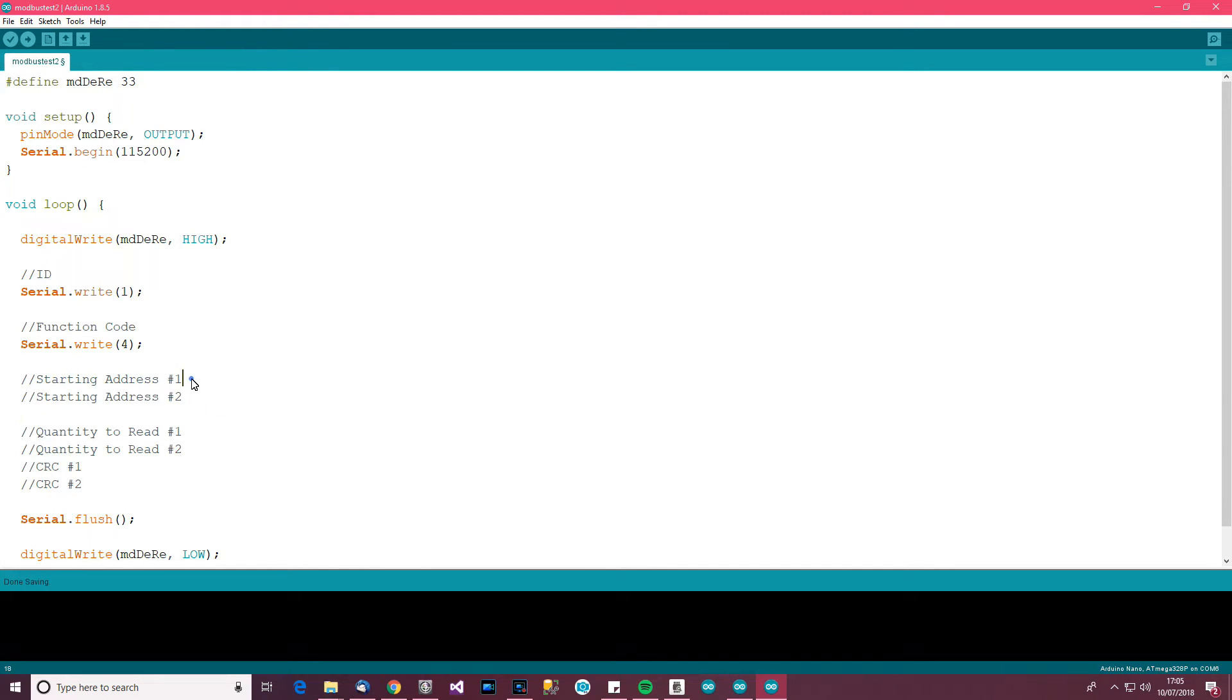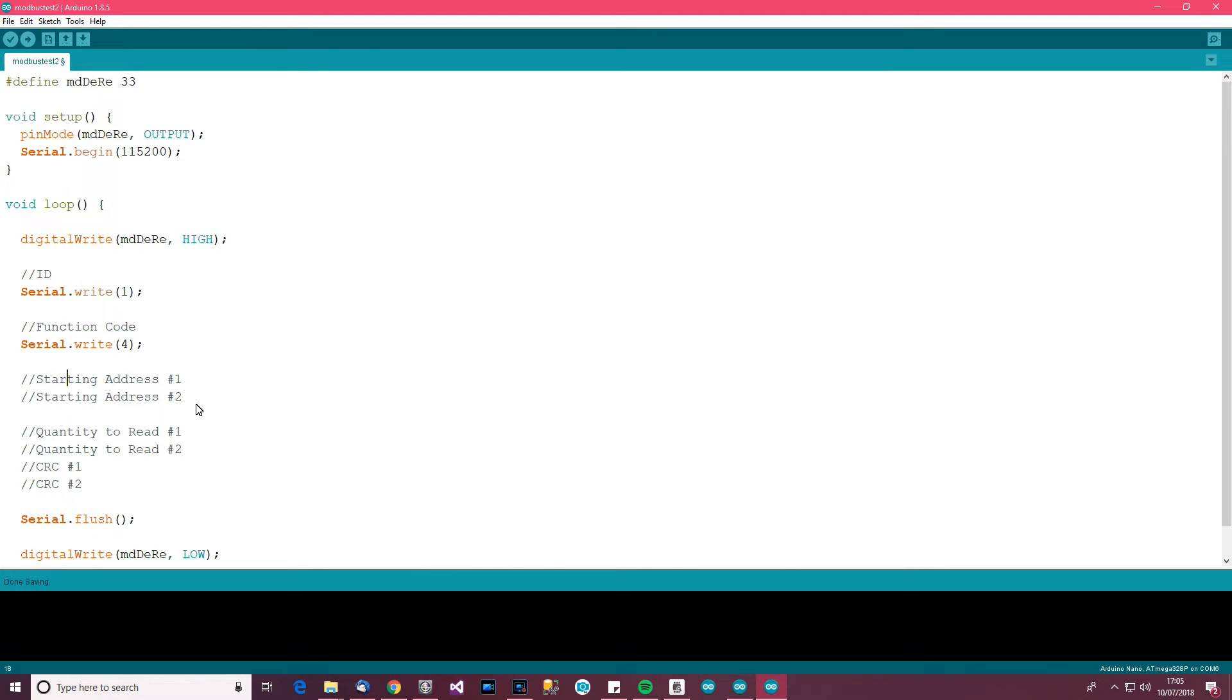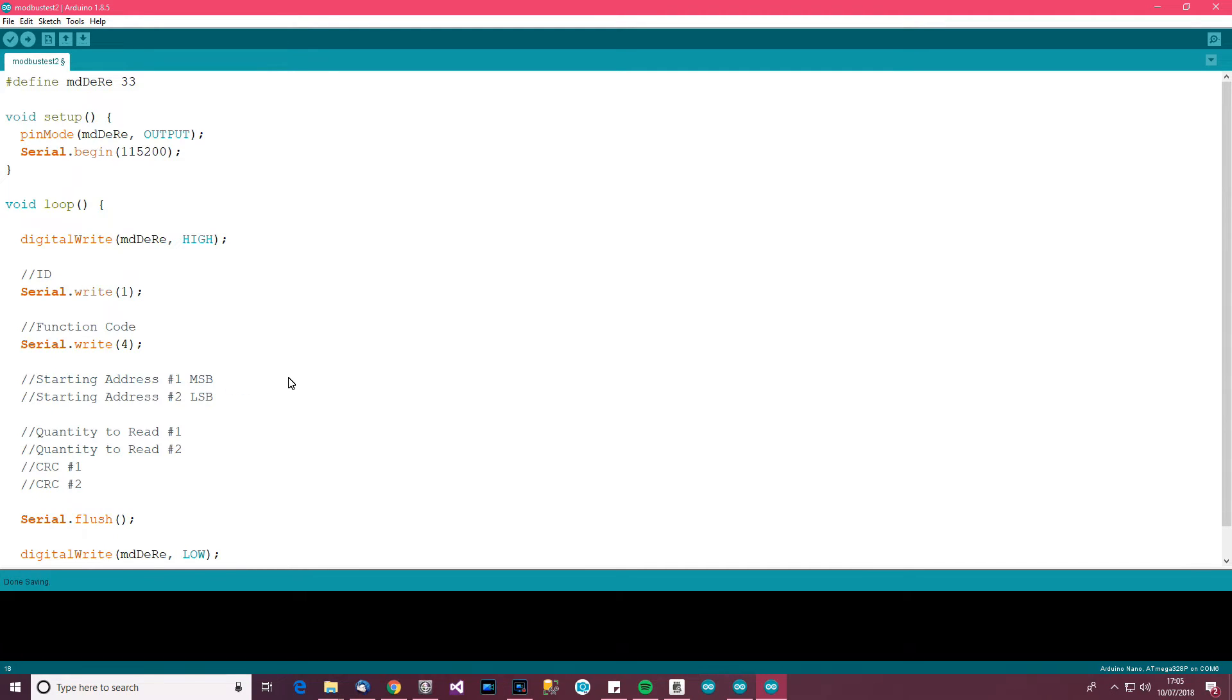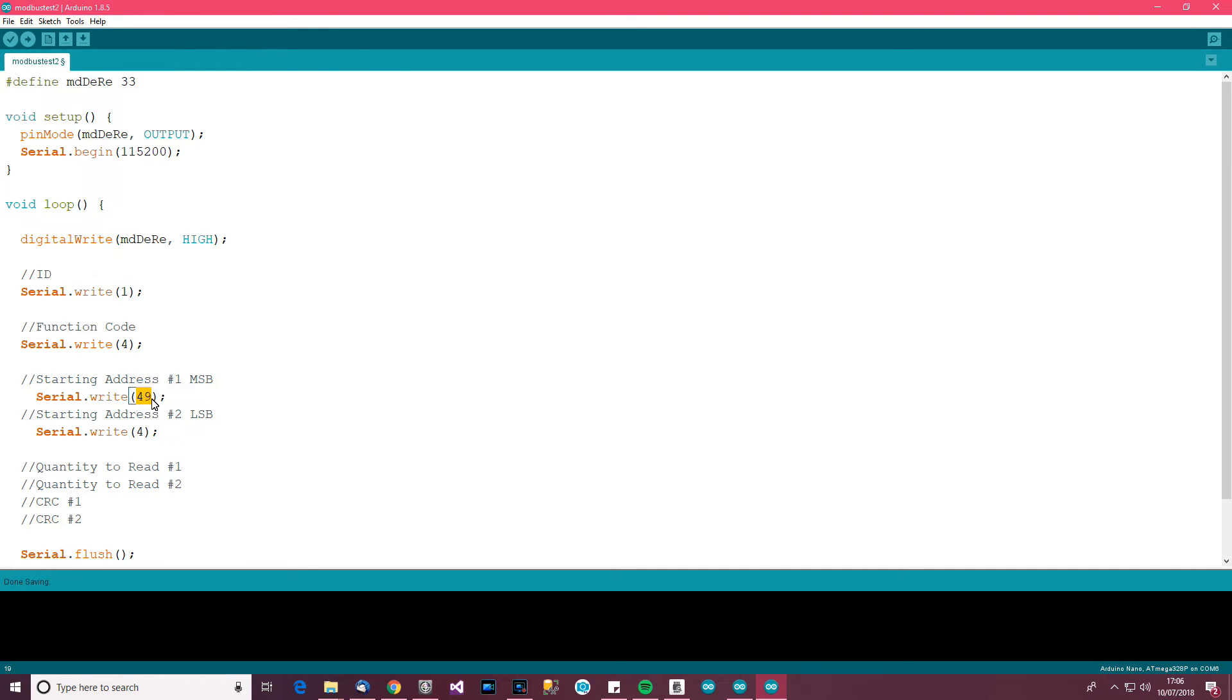So now the next bit is, okay, well which input registers do you want to read? And because there could be quite a lot of input registers, it needs two bytes in order to send the address. And this is where it gets a little bit complicated. You'll have to research how to work this out, I don't want to go into detail with it. Essentially, you need to find that out. So it comes in two parts. The most significant byte, which represents certain numbers, and the least significant byte, which represents the smaller numbers. So here this is MSB, most significant byte. And here this is LSB, least significant byte. And in my case, I want to start from a certain number and it's represented by most significant byte 49. Now I'm sorry that I'm kind of glossing over this, but I suppose that info is for another video. So for me, 49, that byte will represent when combined with this one, it will represent the address that I want.